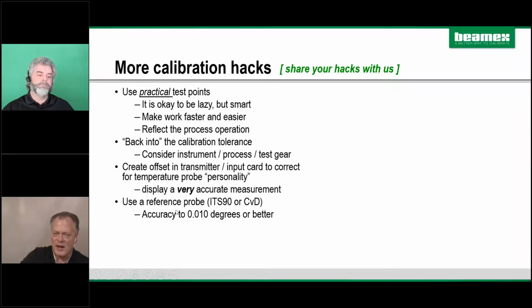And then obviously we've already covered this base, but you need to think about using a more accurate reference probe that has either Callendar van Dusen or ITS-90 coefficients if you're trying to get out to this level. It's really the only way to do it. And one comment on that is that there was a question earlier about what's a dry block. A dry block is simply a unit that generates temperature, as opposed to a bath, which uses a liquid. It's a heater or a chiller.